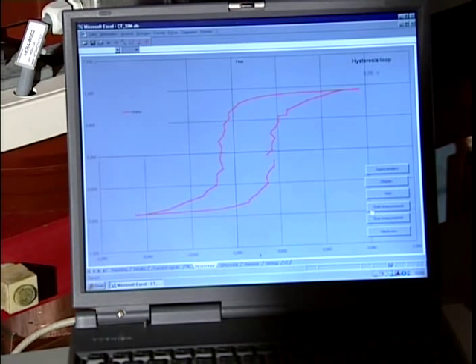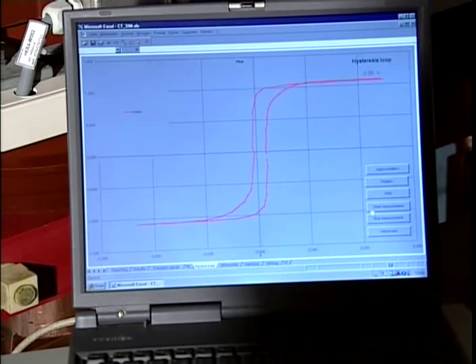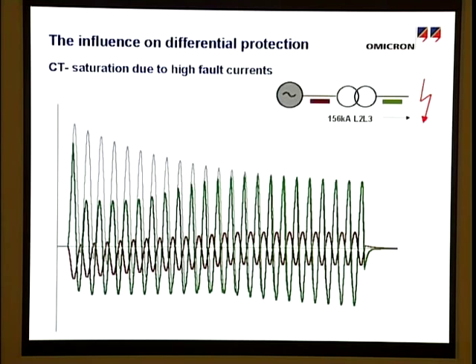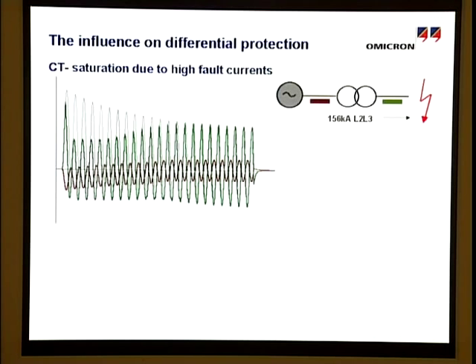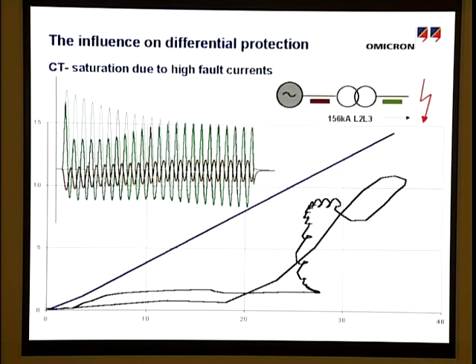Based on the measured hysteresis loop and the other CT parameters already mentioned, a short circuit with 156 kA was simulated. In the result of the relay offline simulation, the locus of the differential and the stabilizing current remain in the stabilizing area, below the tripping characteristic, despite the heavily saturated current, so that stability is provided.